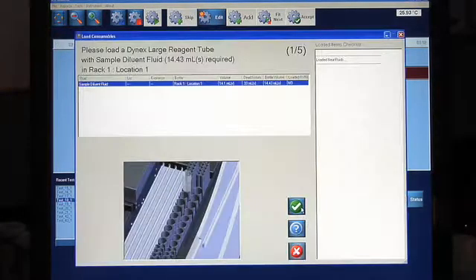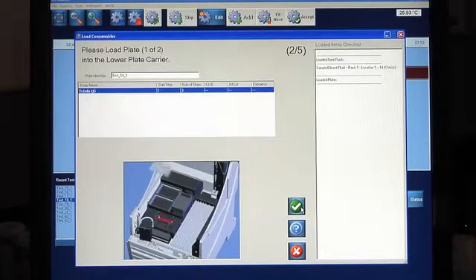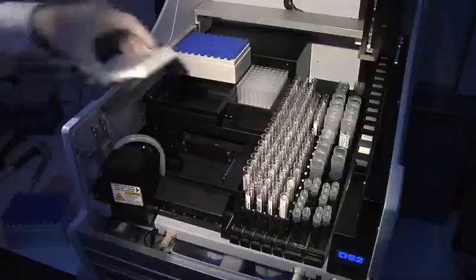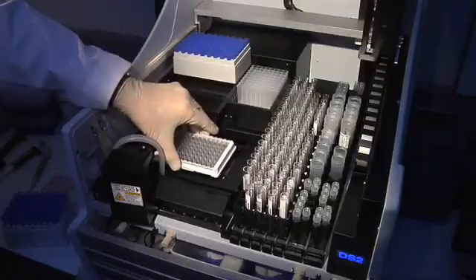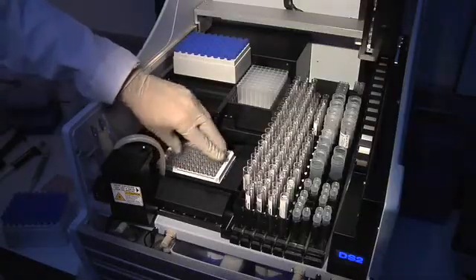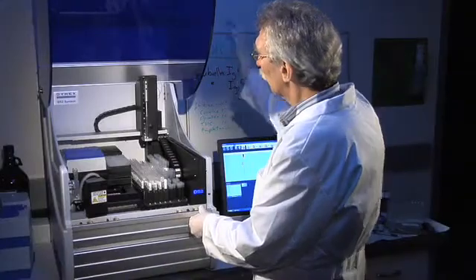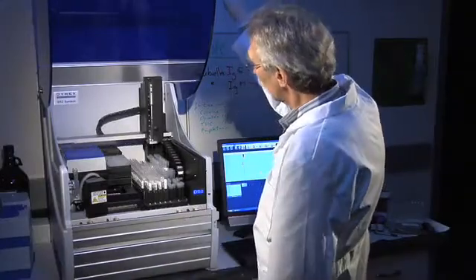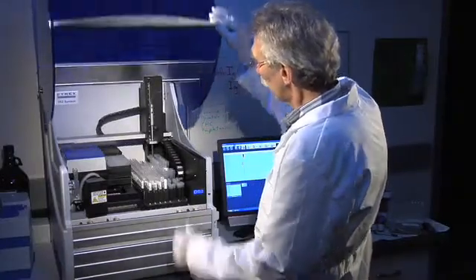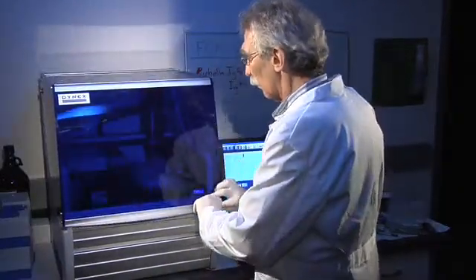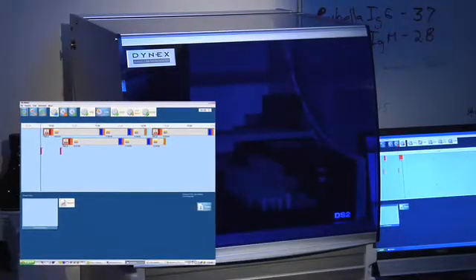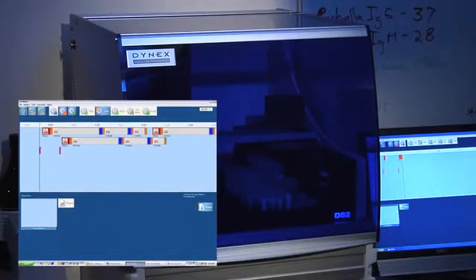The Dynex load wizard prompts you to insert the items required for the selected assays. Animations show the operator exactly where to place each item. Once filled with samples and consumables, the DS2 will take over all operations, freeing the technologist to attend to other tasks. You can even add worklists while another worklist is running.